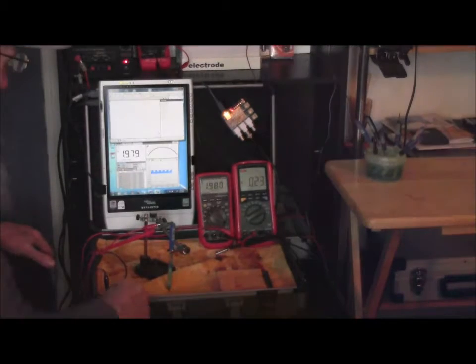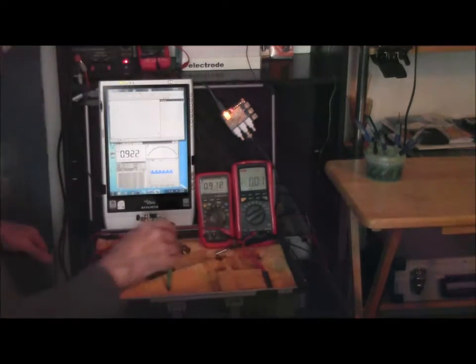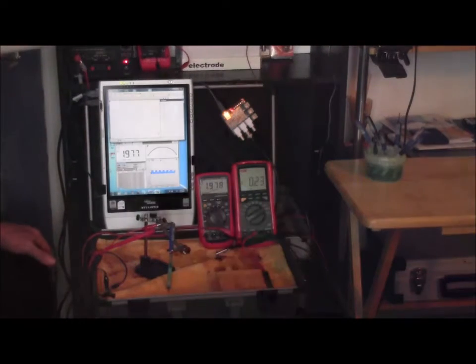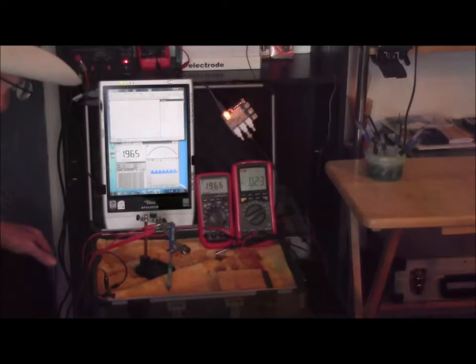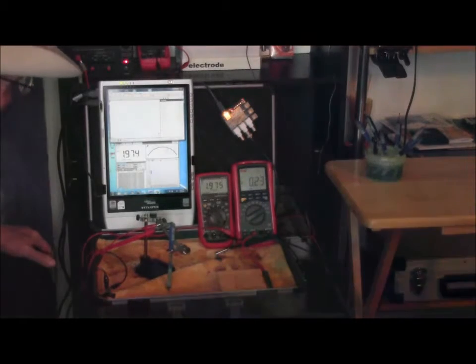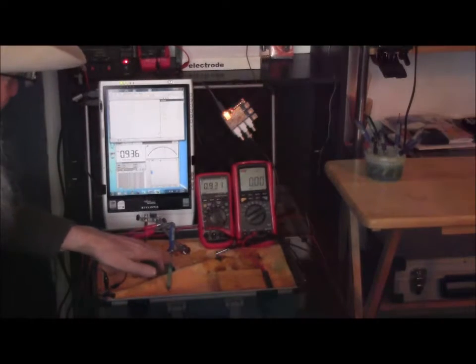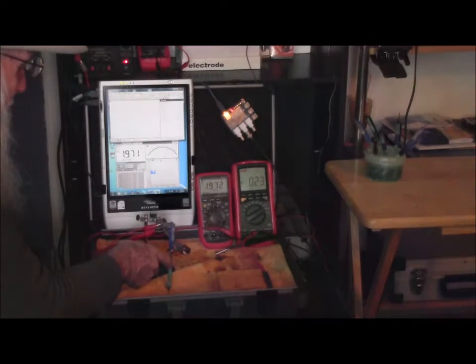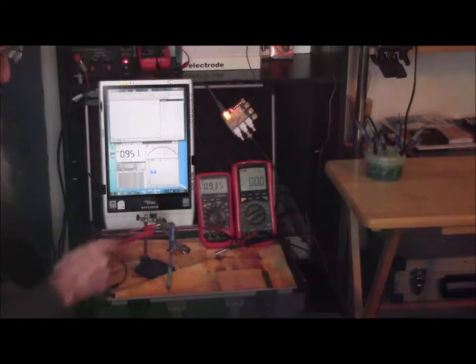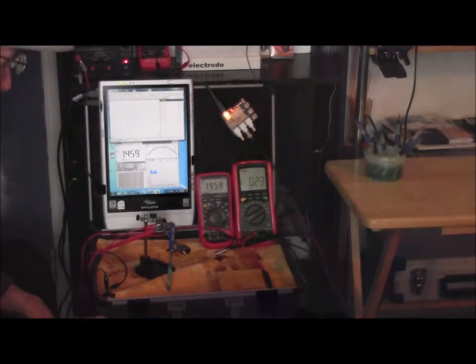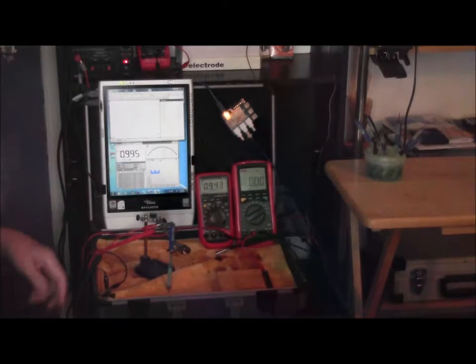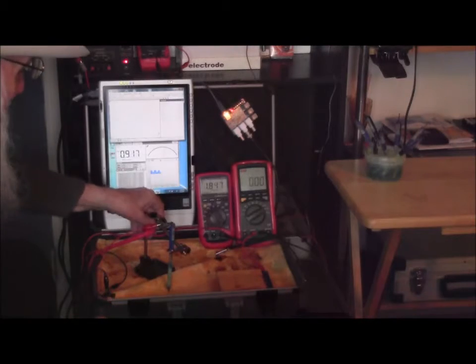When you have more than one coating fault, you have more than one corrosion cell, and therefore you cannot measure the polarised potential against any sort of reference. This reference is the reaction between the copper wire and the saturated solution of copper sulfate. It is not a reference because wherever you move it, the readings are different.